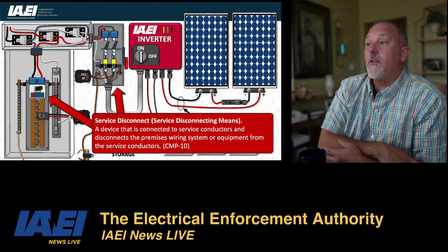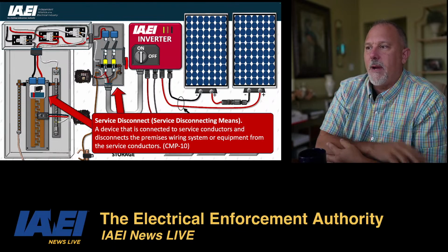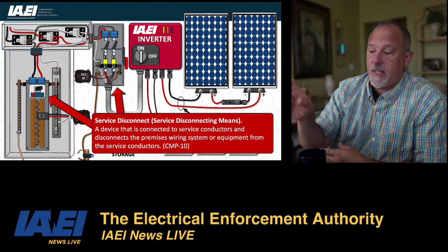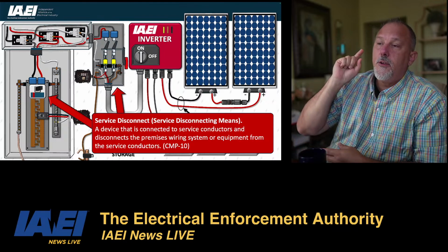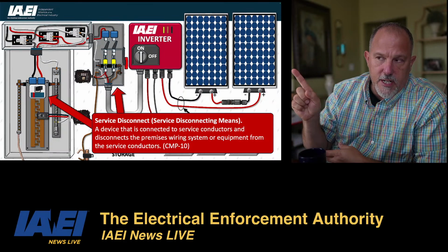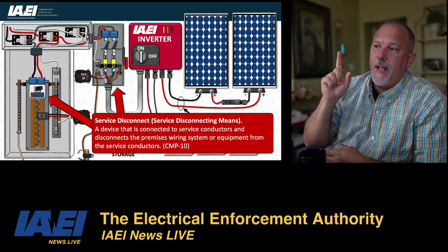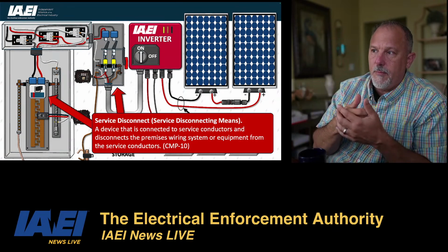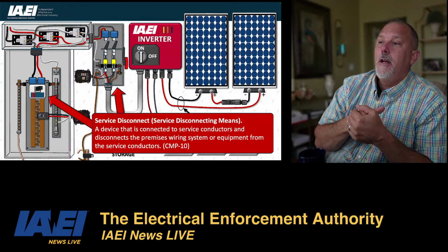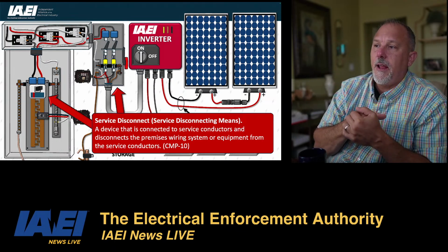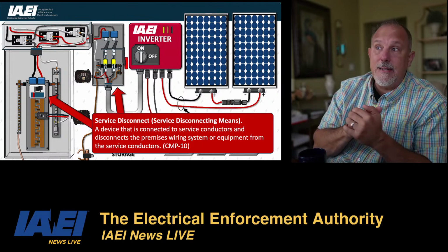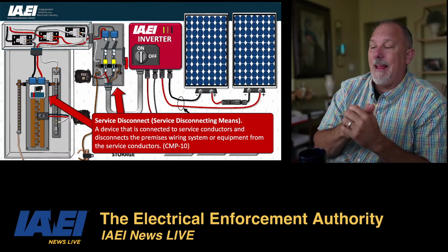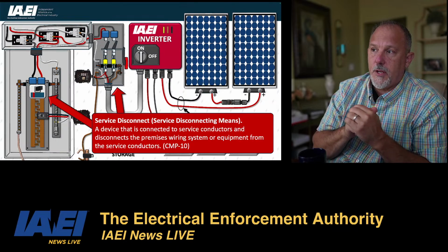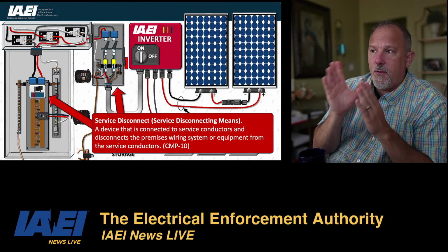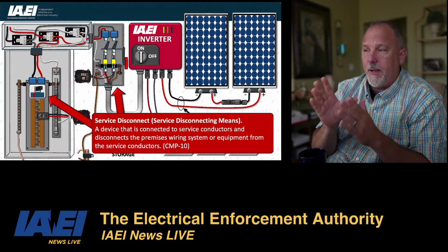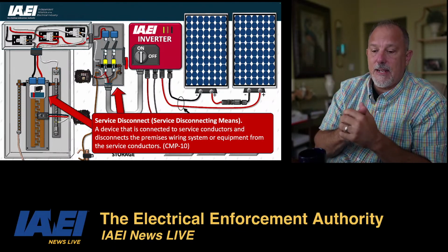So I have the service disconnect. My grounding and bonding is going to occur because it's a service disconnect. I have barriers in place. You have the surge protective device in there. You have your grounding, and you have your bonding. Your main bonding jumper has to be in there. You bring your grounding electrode conductor in there. I have to bring my grounded conductor from my utility in there and land it per the code. So all of the requirements for service equipment will apply to that disconnect switch.